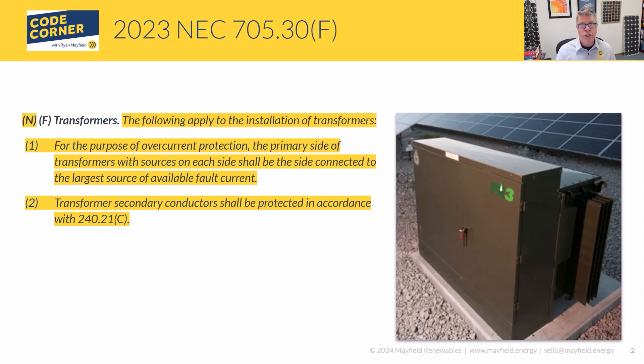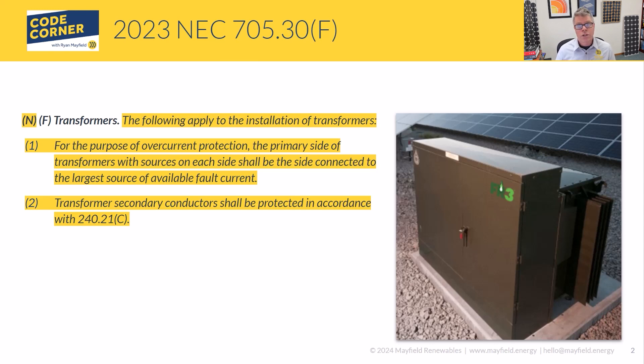Now when we talk about a grid-direct PV system, we see situations where installers are putting in a 480V inverter — so the output of the inverter is 480V — but the utility you're trying to connect to is 208V. So we're stepping 480 down to 208 to go to the utility, reversing the traditional power flow. What number one here is saying is that the primary side will be considered the side connected to the highest available fault current — and in our PV direct systems, that's going to be the utility side.